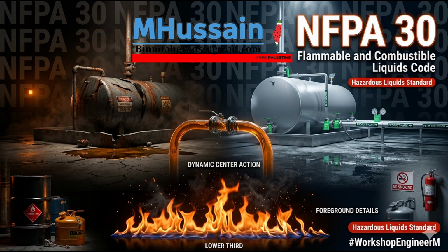We examined the complex fluid mechanics of suppression, understanding why an expanding foam blanket is absolutely necessary to choke the vapor release of a hydrocarbon fire. And we confronted the violent reality of pressure thermodynamics, exploring the catastrophic threat of the BLEVE, and why the smartest engineering decision is often intentionally sacrificing a melting plastic container to avoid a structural detonation. Finally, we applied those same pressure mechanics to the macroscopic scale of above-ground storage tanks. Seeing how spatial isolation, floating roofs, and intentionally frangible seams are meticulously designed to direct and manage catastrophic energy failure.